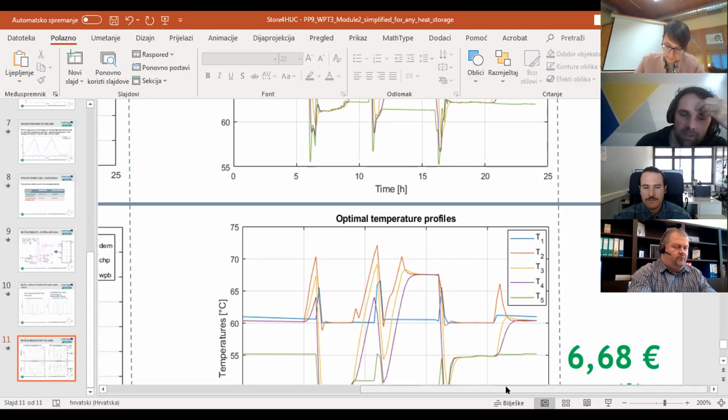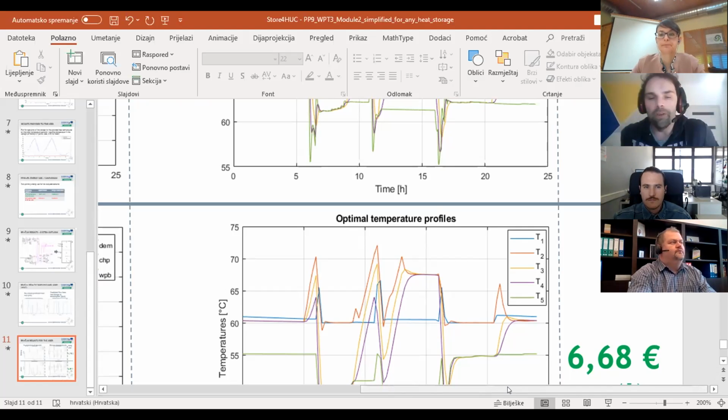But at a certain level in the tank, we would have to have certain temperatures. If we model the tank with the mean temperature and know the temperature difference from bottom to top, we could roughly say what the temperature would be in layer T4, which would then enable us to run the CHP. But it's really specific, an exotic type of heating system, for which you need more dedication.